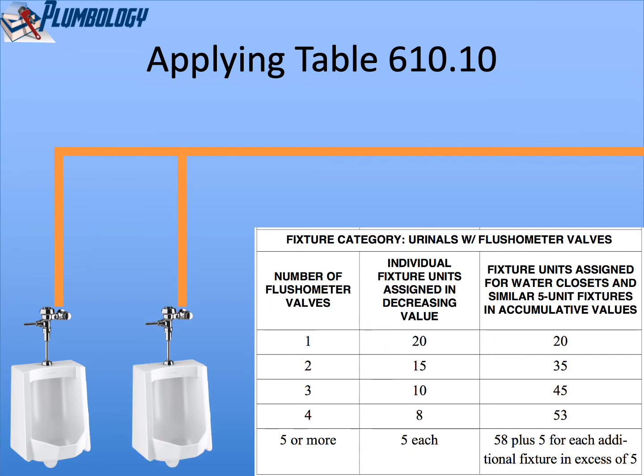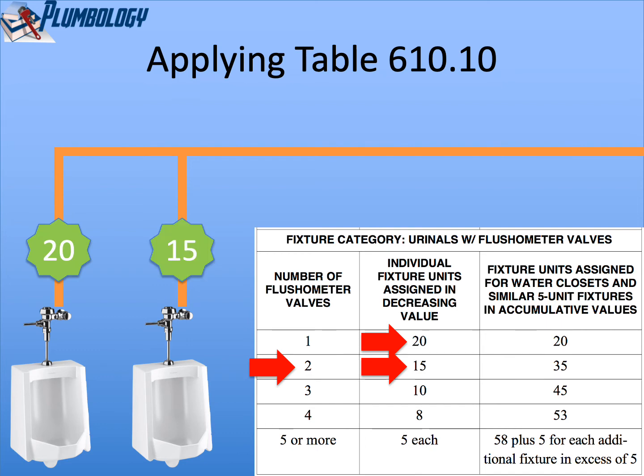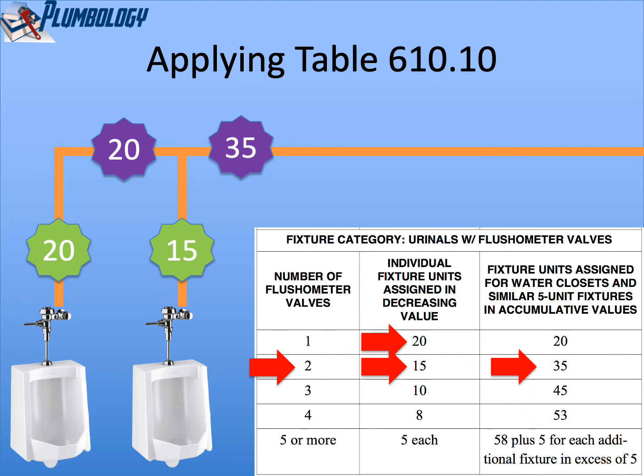If we have two urinal flush valves, finding two on table 610.10, the most remote will be 20 and the second most remote will be 15. We label those flush valves 20 and 15, then give values to the pipe segments: 20 plus 15 equals 35. The table agrees — the cumulative values for two flush valves serving urinals would be 35 fixture units, and we size the branch for 35 water supply fixture units.